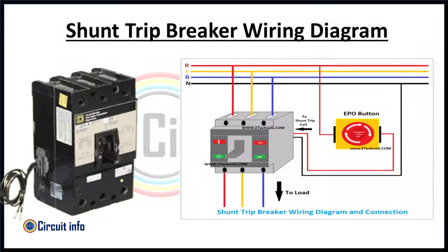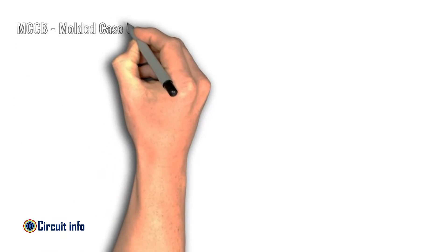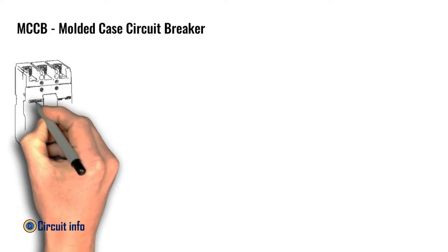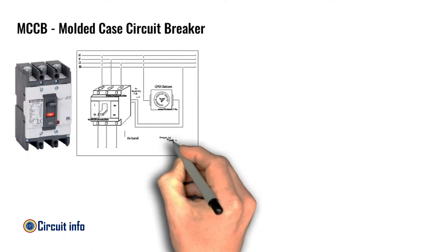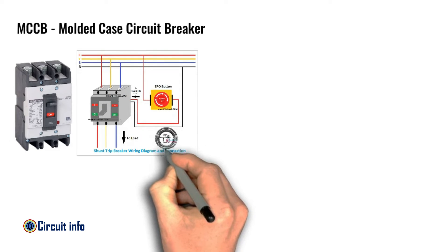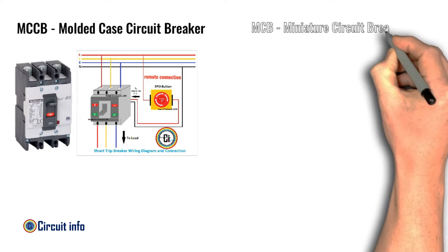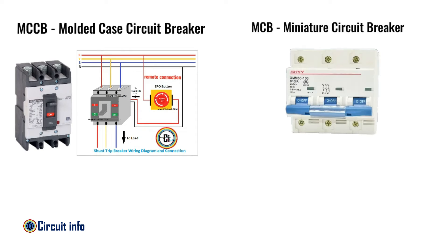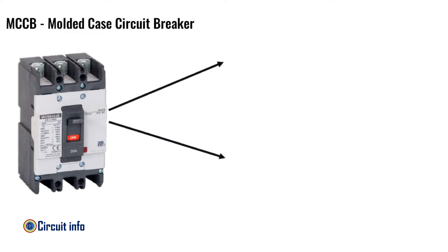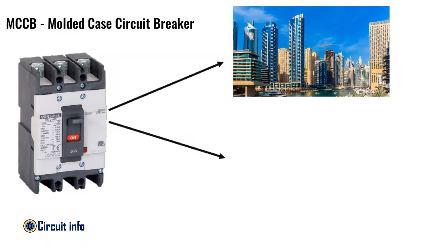The next device is MCCB. The full form of MCCB is Molded Case Circuit Breaker. It is another type of electrical protection device used when load current exceeds the limit of a miniature circuit breaker. MCB handles less than 100 amperes, while MCCB handles up to 2500 amperes. In MCB, remote on/off is not possible, while in MCCB it is possible. MCB is used for low current circuits, but MCCB is used for heavy current circuits such as high power equipment in industries or for commercial purposes.